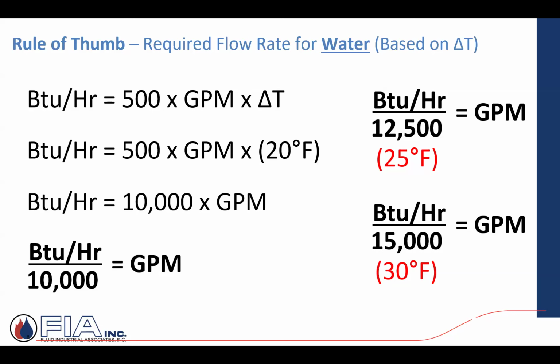Design it on a 5-degree, that's crazy. The flow rate's so high, the pipes are going to be big. And if I design it too wide, now my radiation has to increase and change. So kind of a happy medium, if you will, or economies of scale, 20, 30 degrees. When we get into primary, secondary, and we start talking different flow rates mixing, when you start playing with high delta Ts, it absolutely is a factor in a positive way, and it will work, and we'll get to that in a couple of weeks, I think.